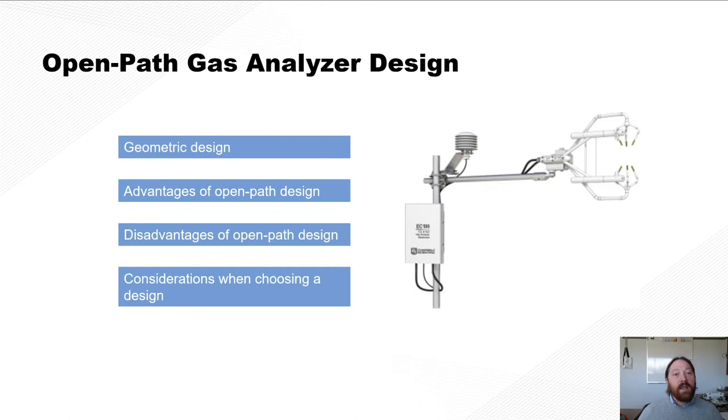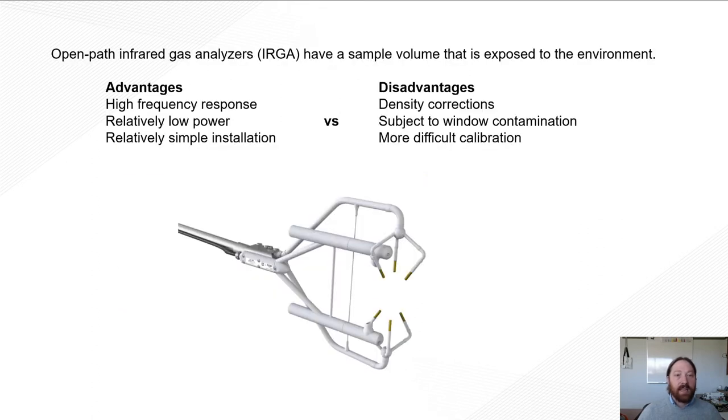So when we look at the open path gas analyzer design, we have to consider the geometric design, our advantages and disadvantages, and then also considerations when we're choosing which design to go with. So the open path design literally means that it's exposed to the environment. So it is an open sampling volume. So where we have a source on the top and a detector on the bottom, the volume between those two is our measurement volume, and it's open to the environment. Same thing with a sonic anemometer. This volume here is exposed to the environment and is therefore open.